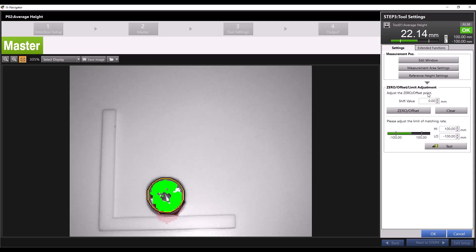Let's say this is my master part and I want to read how far off future parts are from this master. I have my shift value set to zero so I can click the zero offset button and that will change my reading to zero. Now I can set my tolerances based on the master part.